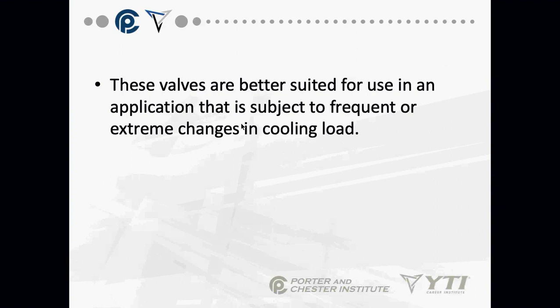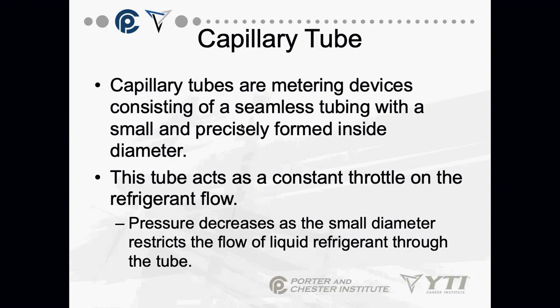So the TXVs and the adjustable orifices automatically adjust the refrigerant flow to these changes in cooling loads. That's what makes them so efficient. Okay, they most often sense the evaporator temperature or your superheat, and they adjust based on that.